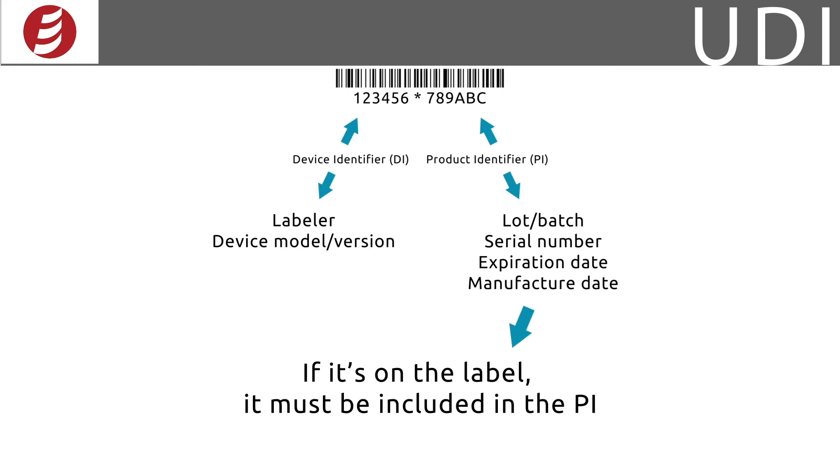Each component, subsystem, or accessory that is considered a medical device needs a separate UDI unless the components are part of a kit or medical device system that is marked with its own UDI.